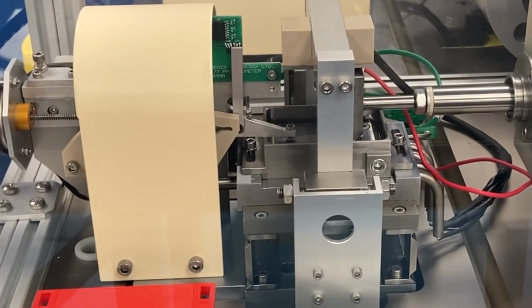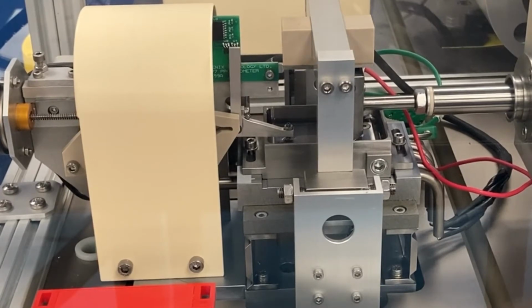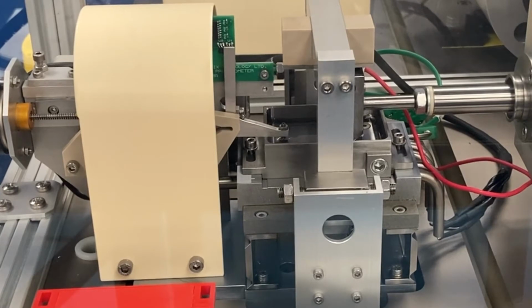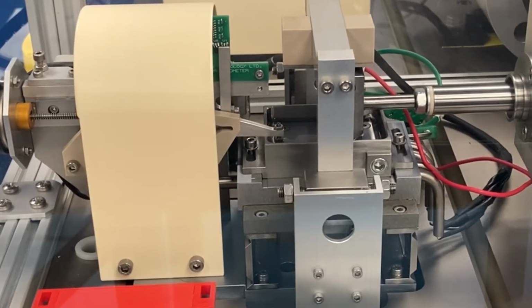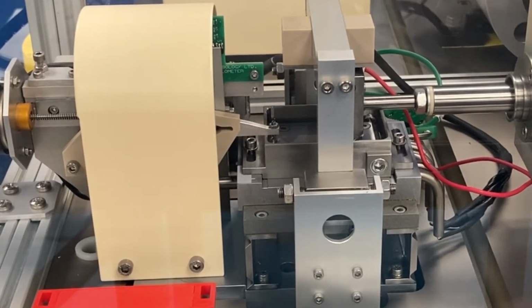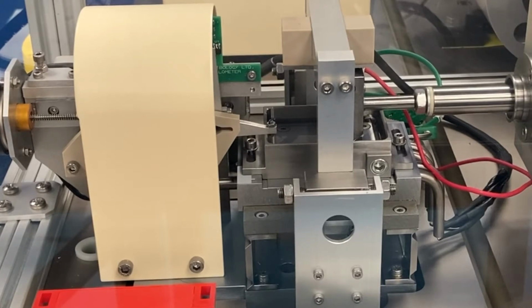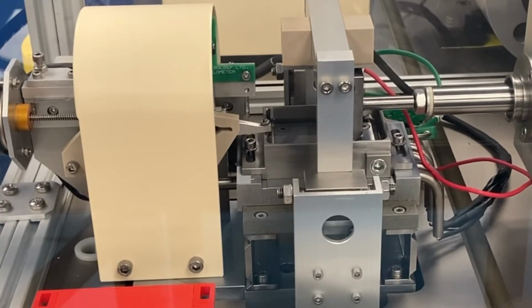As the profilometer is not mounted directly on the specimen's surface, measurements can be affected by deflection of the machine and test assembly. These can be corrected by referring all measurements to the unworn part of the specimen's surface, but a simpler solution is to make sure that the load applied to the specimen assembly during a profile measurement cycle is always the same.